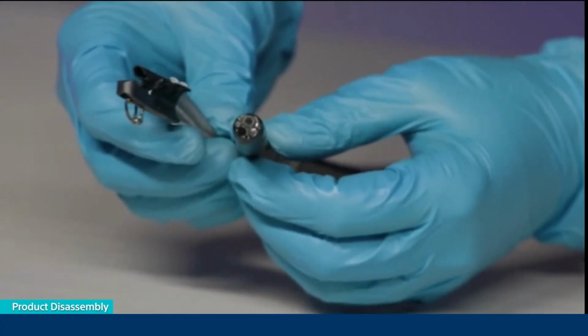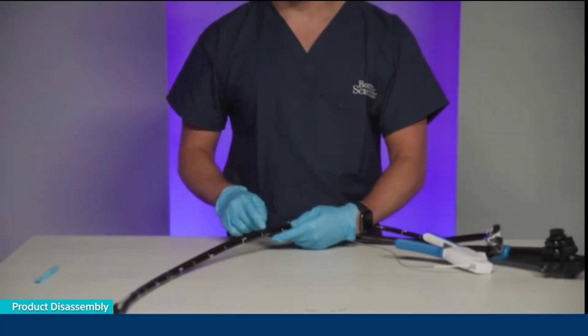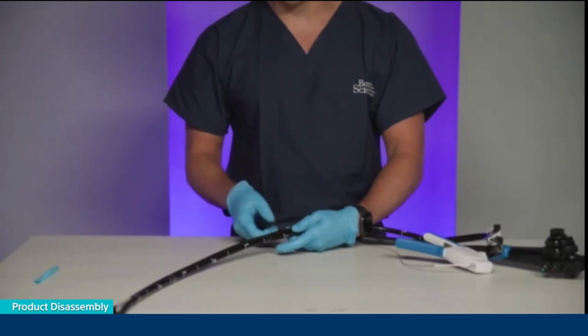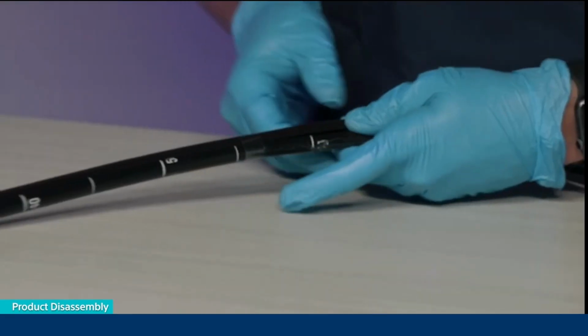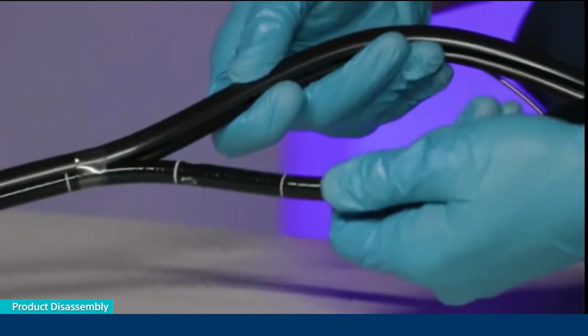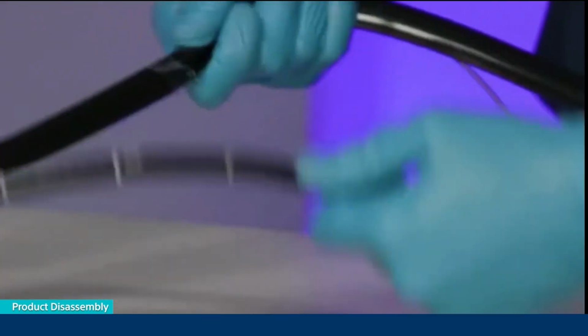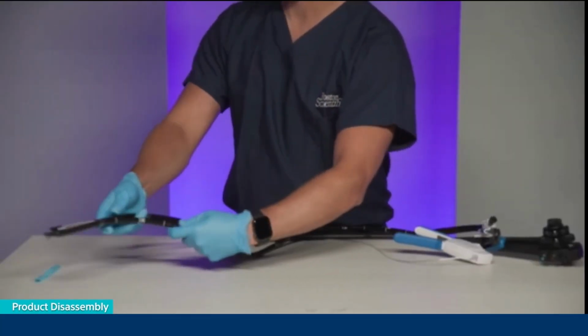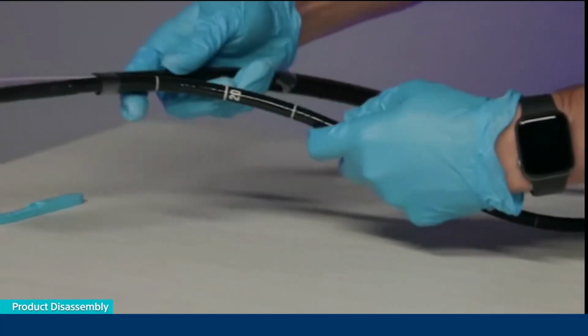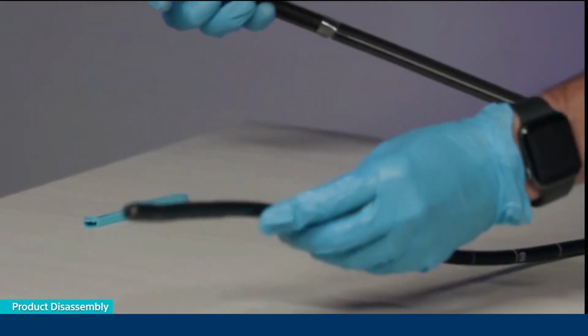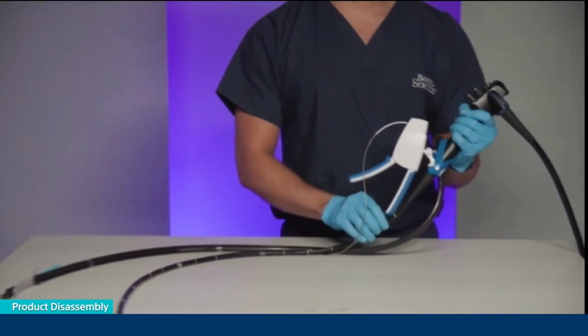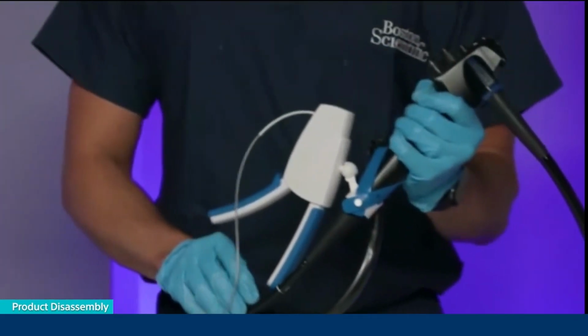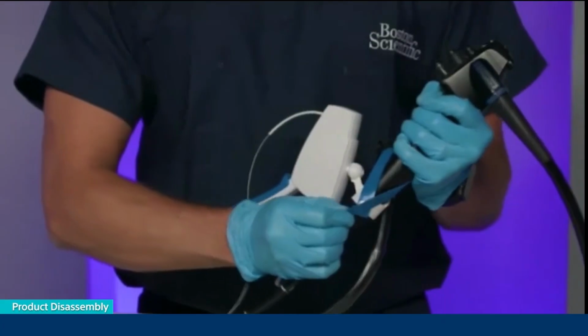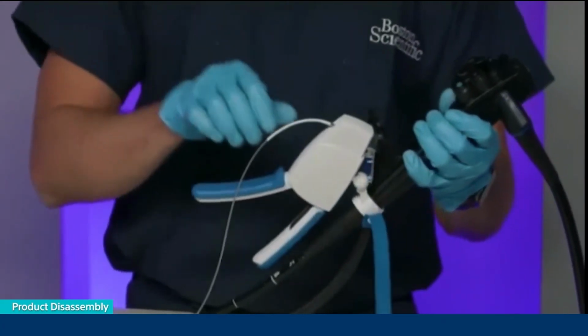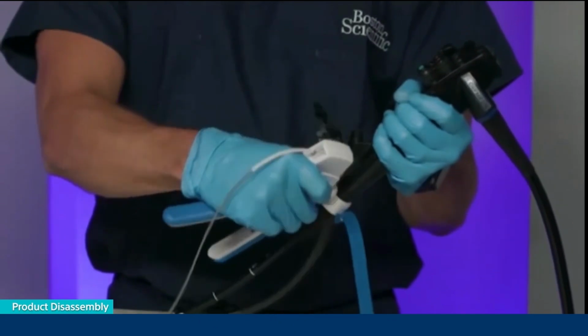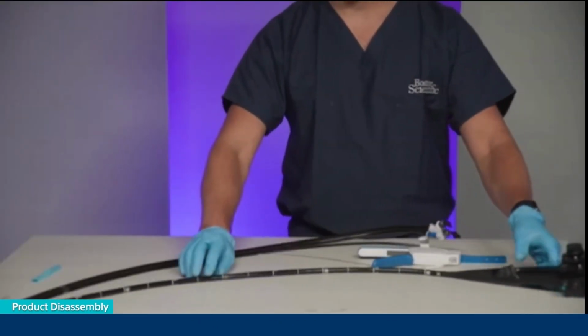Once your end cap is disengaged, you're actually going to then travel back up towards the top of the scope. Each of the sheath tapes are perforated, so all one has to do is separate the scope and the sheath and pull apart. Work your way down proximal to distal. Your device should come free. Last step, back at the handle, move your blue strap back over, and then pull the handle down and off the device.